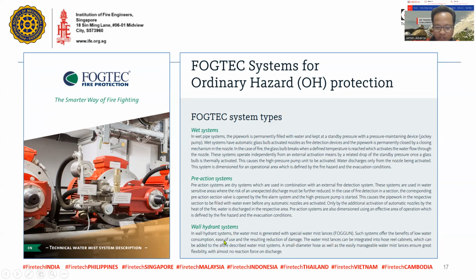There is also a hydrant system wherein, instead of using a hose rack, class 1, class 2, class 3 fire hose and a cabinet, in a water mist system there is what we call the fog gun. It's a gun wherein mist of water will come out. Now, what's the very big difference from conventional deluge, wet and hydrant? In conventional systems, because the system runs on lower pressure, that is 120 to 150 psi operating pressure, the tendency is to have a bigger pipe diameter. On a water mist system, the biggest pipe diameter is just 2 inches. You heard it right. It's just 2 inches, stainless steel.